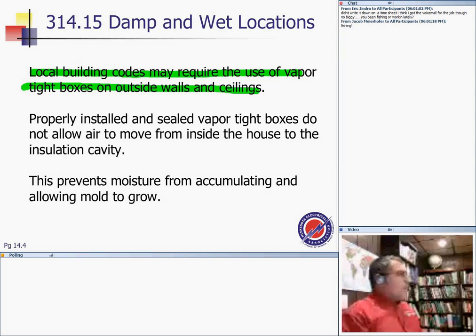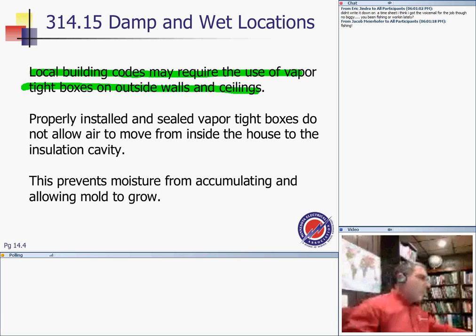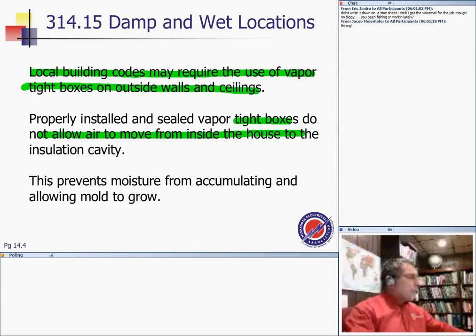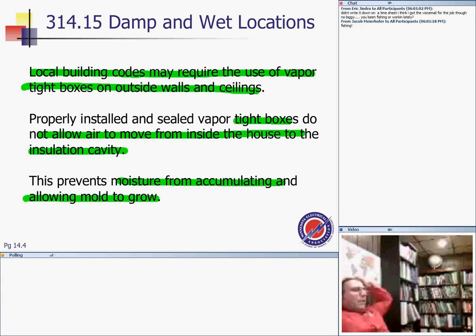The building code may require the use of vapor tight boxes on outside walls and ceilings. That's weatherproof boxes. Do you guys use them? A lot enforce them on an outside wall. So yeah, weatherproof boxes. I think there was a picture of it on the slide. Any boxes on outside walls and ceilings should be vapor tight. And here, guys, these are so installed and sealed. Tight boxes do not allow the air to move from inside the house to the insulation cavity, so it saves energy. And as a result of this, no moisture will be accumulating, and then no mold will be growing, right, into the basement. So two birds with one stone.